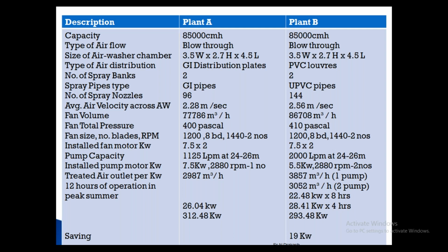Then the number of spray banks: there were 2 banks. The spray pipes were GI pipes earlier, and with GI pipes there will normally be scale formation and other problems, so we converted them to UPVC pipes. The number of spray nozzles went from 96 to 144, because we converted the single pump feeding two spray banks into two independent spray banks with 2 pumps.